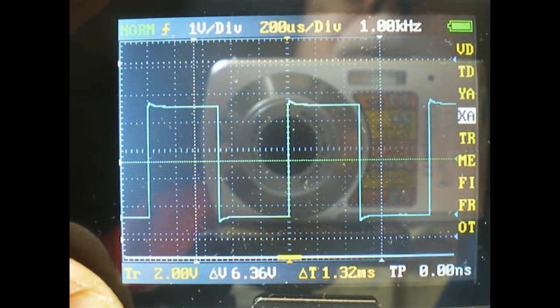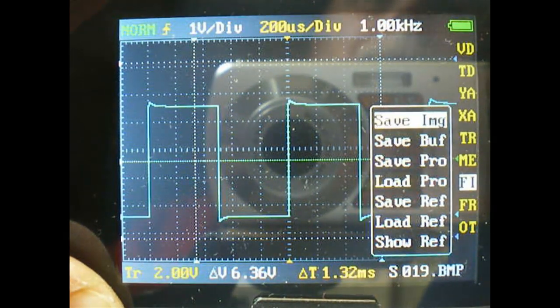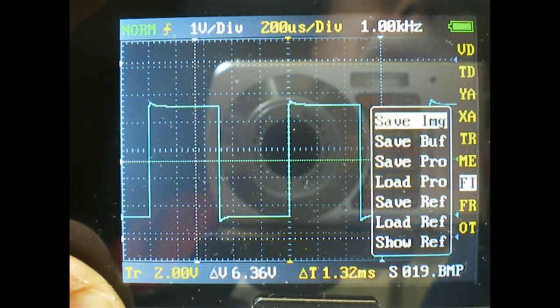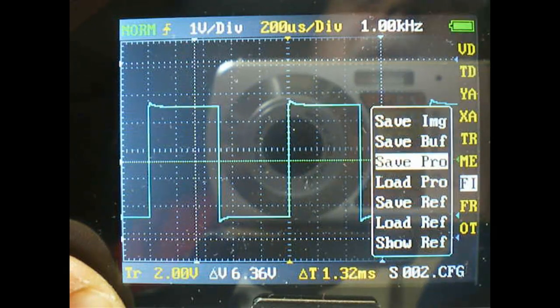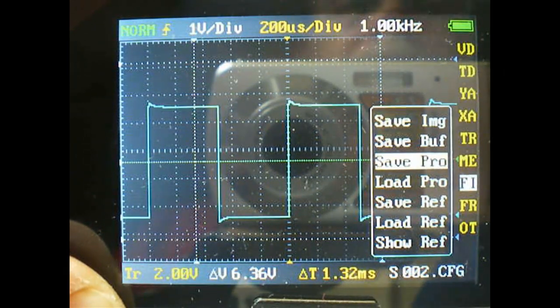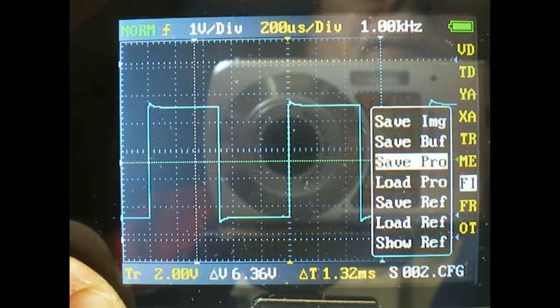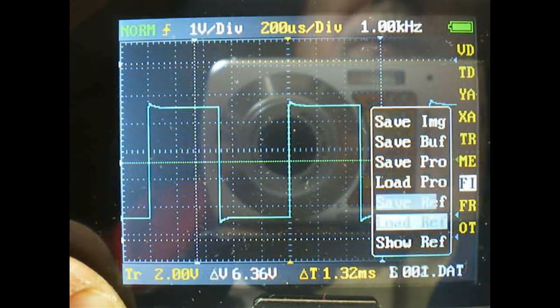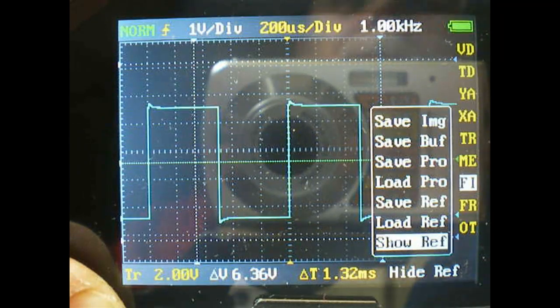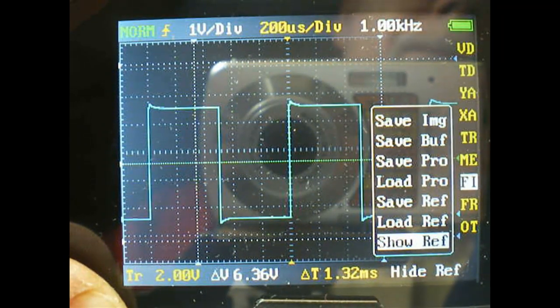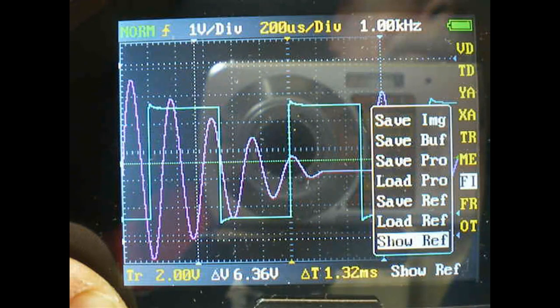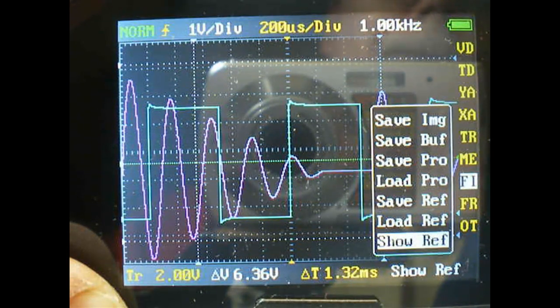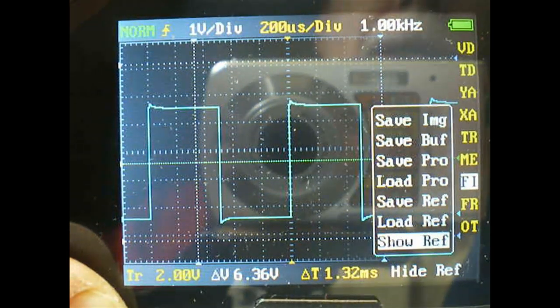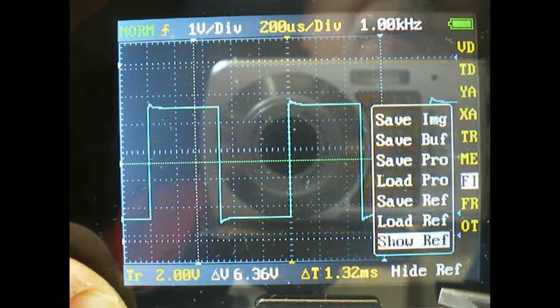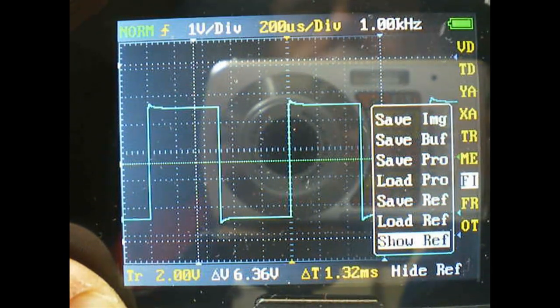We also have a file input-output system right here. We can save images, we can save the entire acquisition buffer, we can save profiles to an SD card that's removable. It's a hot swappable SD card. We can load profiles, we can save, load, and show reference waveforms on top of the existing waveform. For example, there's a reference waveform on top of the square wave. We can also hide that reference, which is shown down here. Show and hide. It has a battery status indicator.